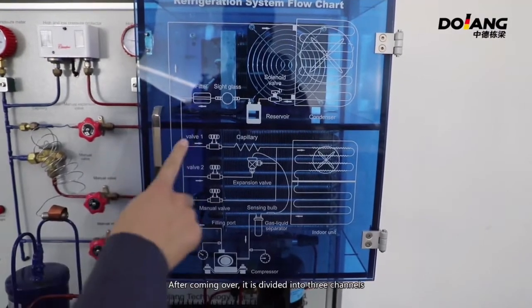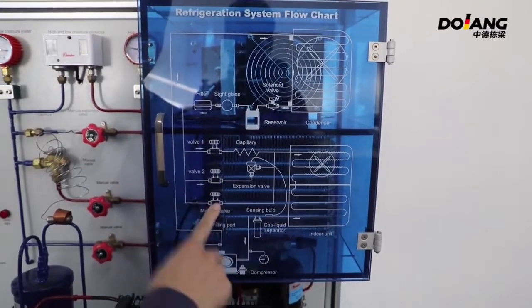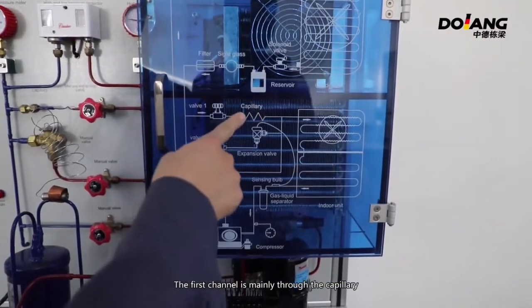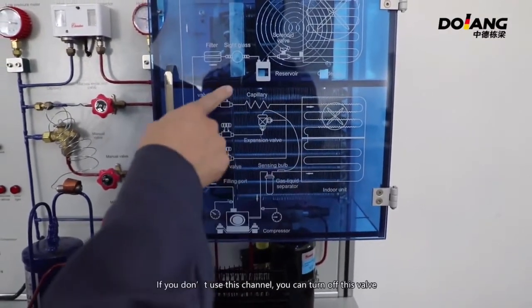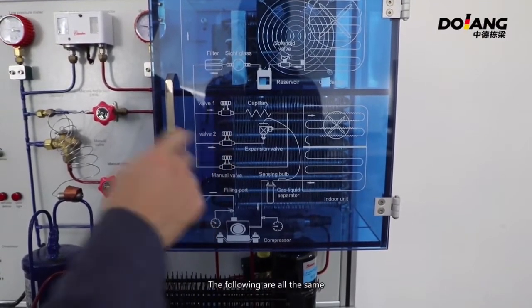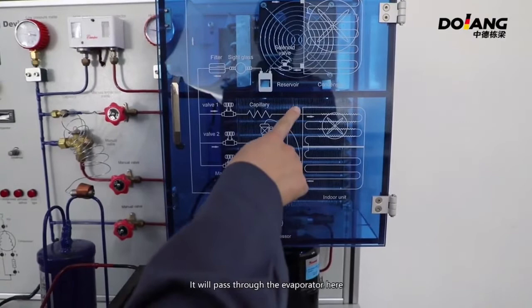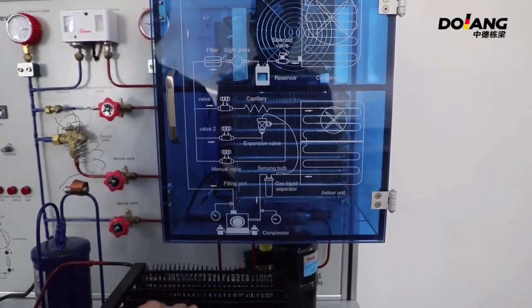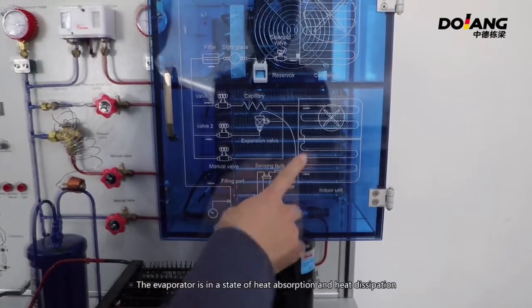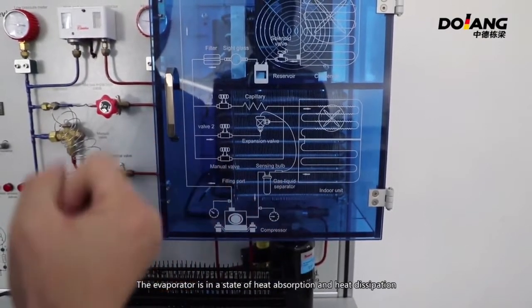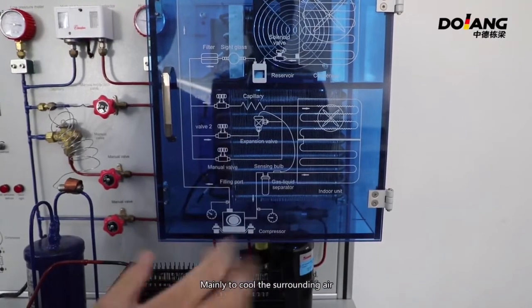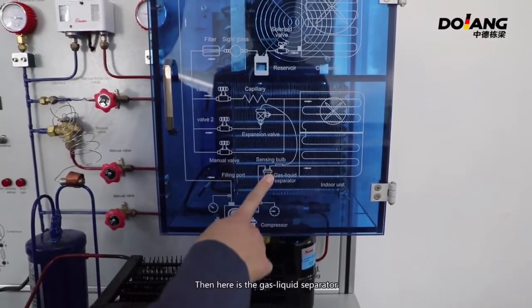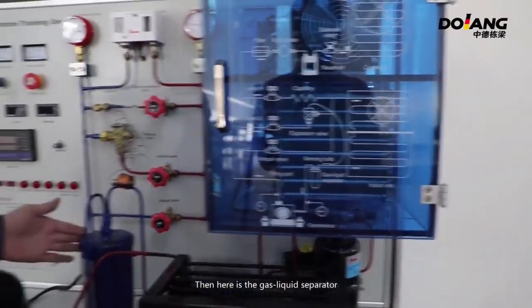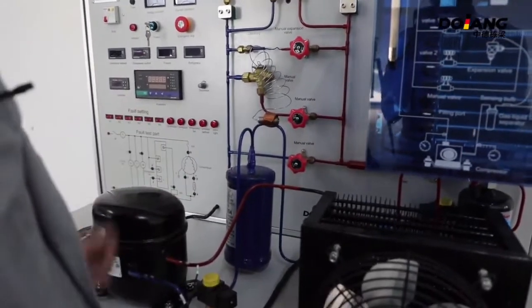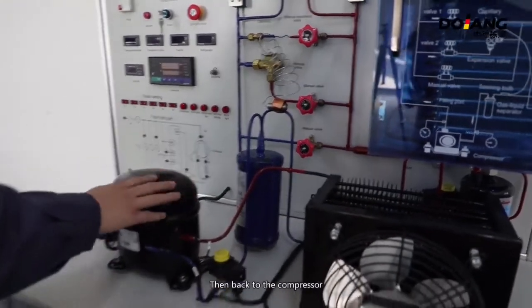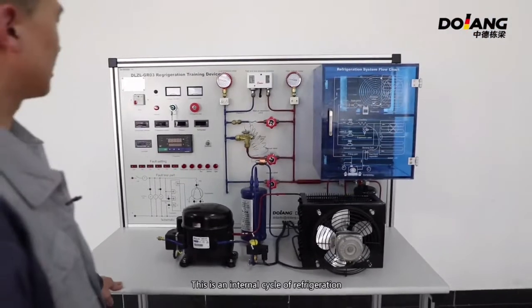After coming over, it is divided into 3 channels. The first channel is mainly through the capillary. If you don't use this channel, you can turn off this valve. The following are the same. It will pass through the evaporator here. The evaporator is in a state of heat absorption, mainly to cool the surrounding air. Then here is a gas liquid separator. Then back to the compressor. This is the internal cycle of refrigeration.